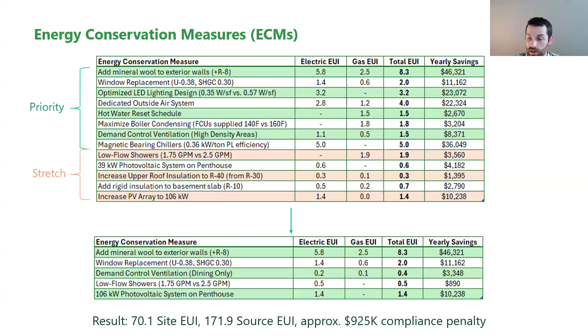They have their strong preferences, but we're trying to show, using our energy modeling results, that making the case for a different HVAC system. And our goal here was a water source heat pump system, which would be significantly more efficient than the fan coils. And we had a few selling points here just beyond the financial penalty through BEPS. And it actually turns out this would have a lower first cost just because we're switching to a 2-pipe hydronic system versus the 4-pipe fan coils. So we're eliminating half the piping in the building, as well as we're not needing to replace the existing chiller, just the cooling tower only.